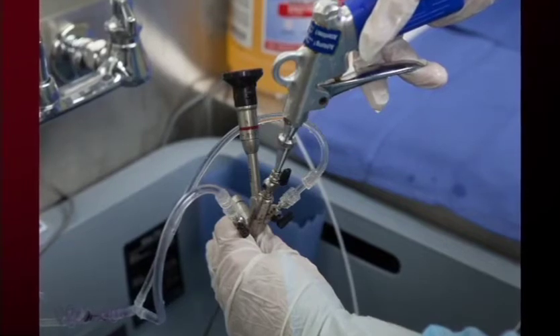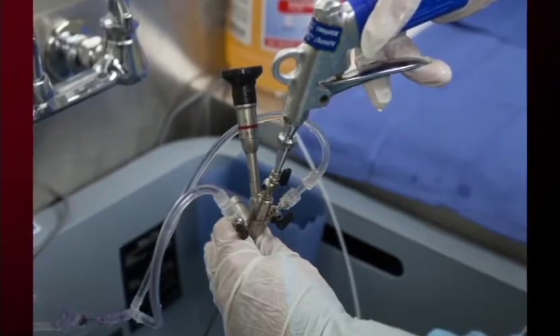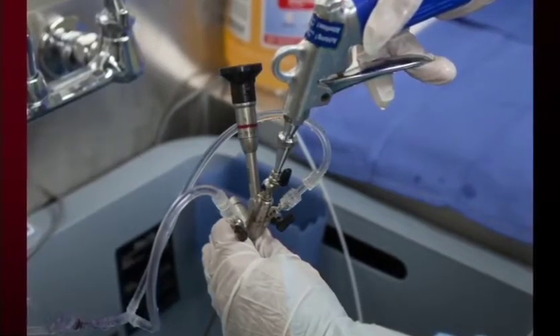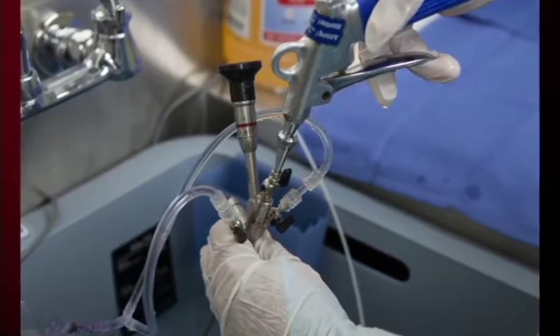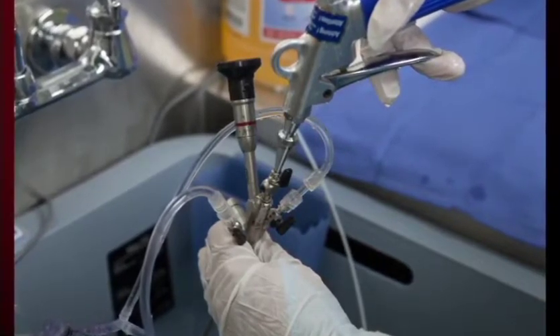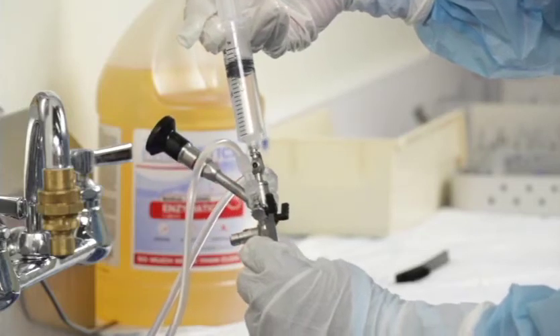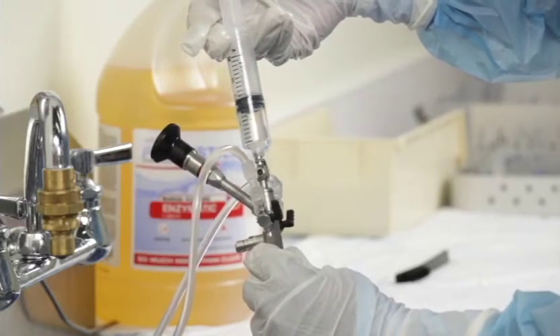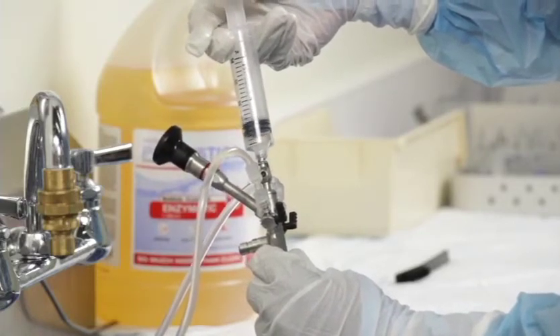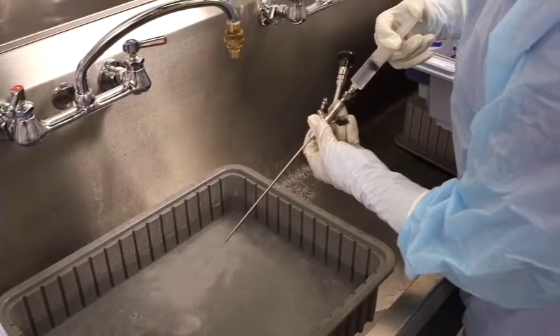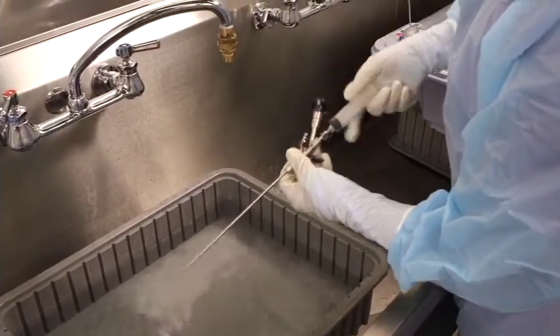After brushing, flush the channels with enzymatic detergent solution using a pressure device, like the one shown here, or a 20 cc syringe to remove any loose debris. Rinse the endoscope's channels with processed water and a water pistol, a pressure device, or a 20 cc syringe. Rinse thoroughly to remove all detergent residue from the scope or channels.